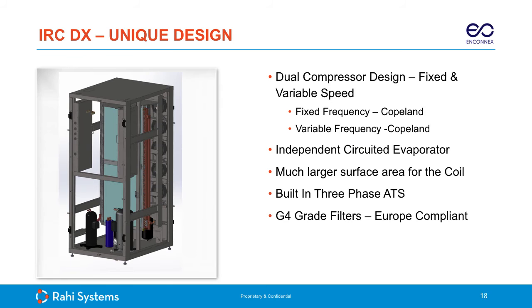So on the next slide, a little bit about the DX system, or the refrigerant-based or glycol-based compressorized system. Again, exact same form factor as the chill water system. It's got dual compressors, sourced by Copeland, which is a very, very popular and reliable brand. It's got variable capacity, so it can match IT load all the way from 10% up to 100% load. The coil is also designed around a dual circuit, which I consider a reliability feature. So for instance, if you lose one compressor, you won't lose the whole system, so you can still run the system at, say, a part load or half load.